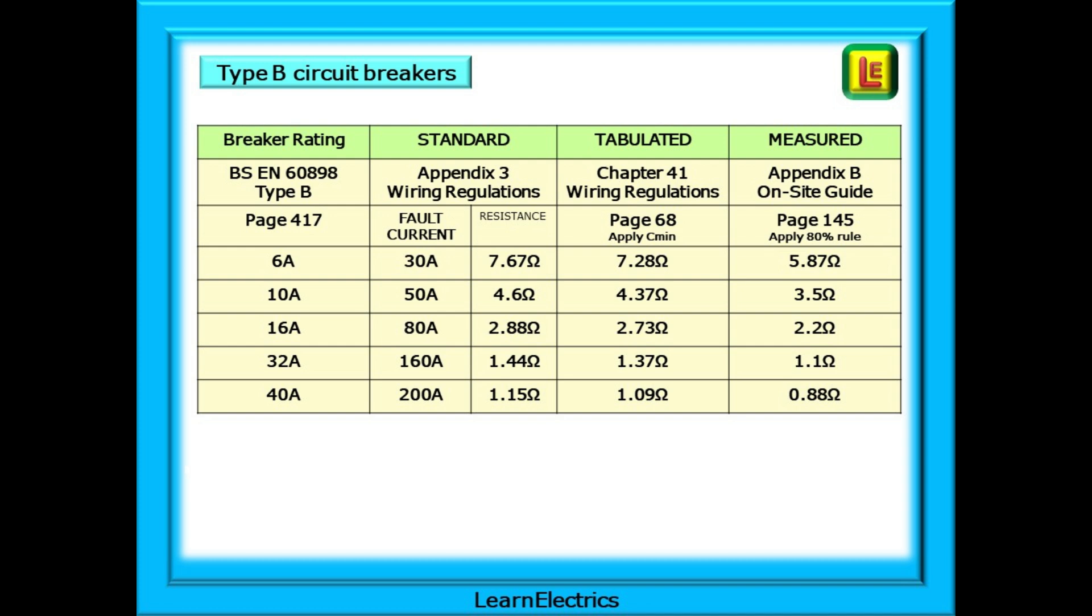And finally, this table shows the progression from the standard values through the tabulated values and on to the measured ZS values for a selection of Type-B breakers. Similar to the previous table, it shows that as the breaker rating increases, the required fault current increases and the maximum ZS values decrease. A similar pattern with totally different results would be obtained from Type-C and Type-D breakers. And it might be worth your time to make the same calculations as here, but starting with the C and D data that is shown in Appendix 3 on pages 418 and 419. I'll leave that one with you.